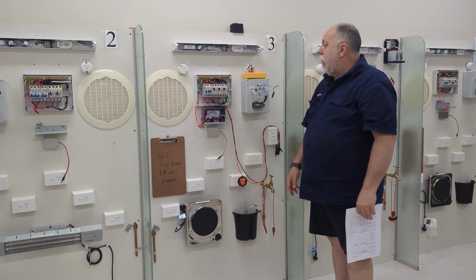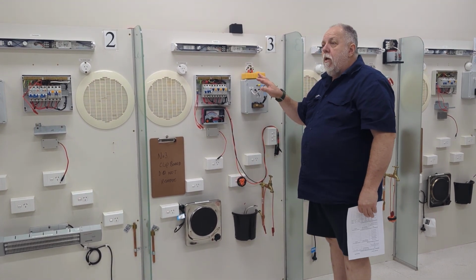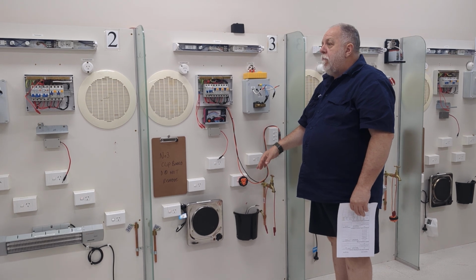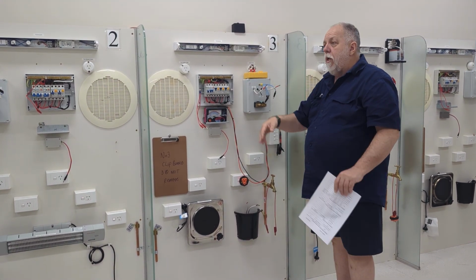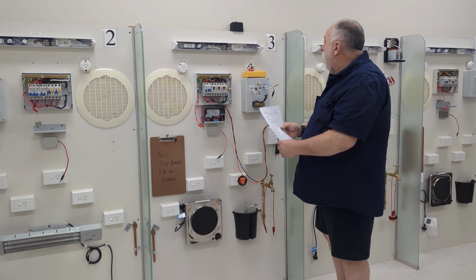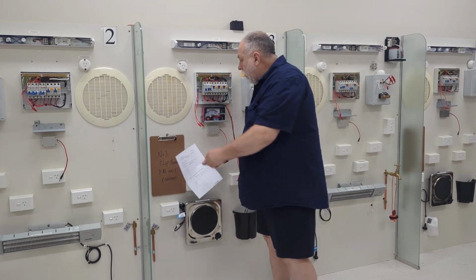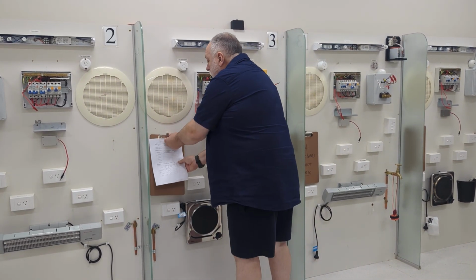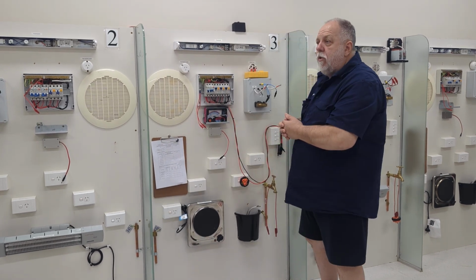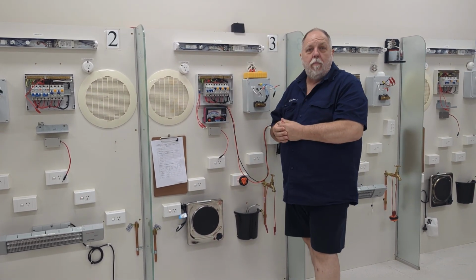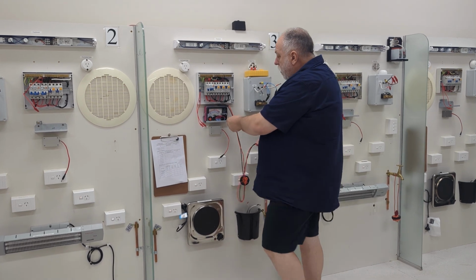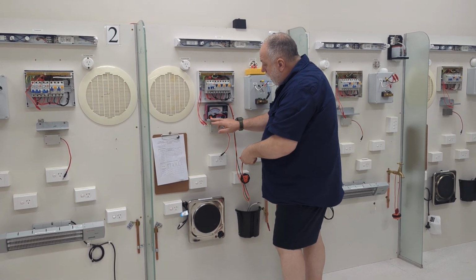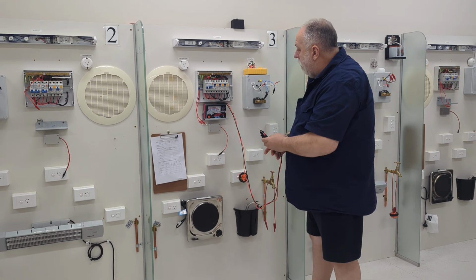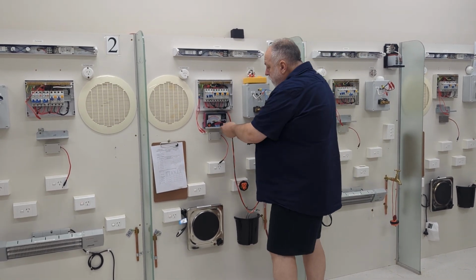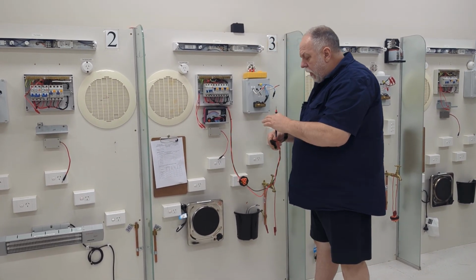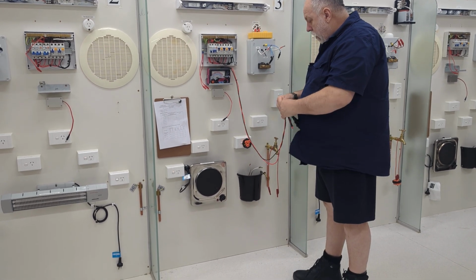All right, so earthing's the main thing we have to establish on doing an installation first. Once we have all our reference points done and pick up what's not earth and earth, then we can head off. So the first is the main earth, all right? What's the first test I need to do? When I'm testing, I've got this meter, got down the truck, what's the first test I've got to do? Battery check. All right, I want to make sure my battery's working correctly. So I go to my battery check down here, push my button in. That's reading, pumping up nice and strong. I'm happy with that. The next one, I go to zero my meter out, all right?